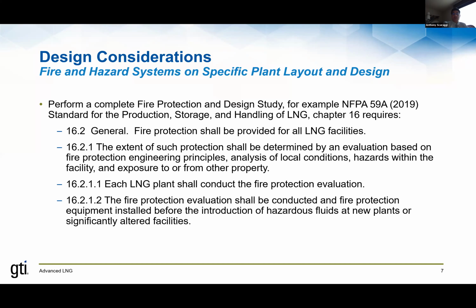So one particular standard, NFPA 59A, has detailed requirements, and this is a section from 59A, on what needs to be done for that fire study. NFPA 59A is a standard that's been adopted by many different municipalities and countries. It's a well-known, well-developed standard that's used for the design, construction, operation, and maintenance of LNG facilities, and this is some of the language in that standard around the requirements of a hazard analysis or fire protection study.